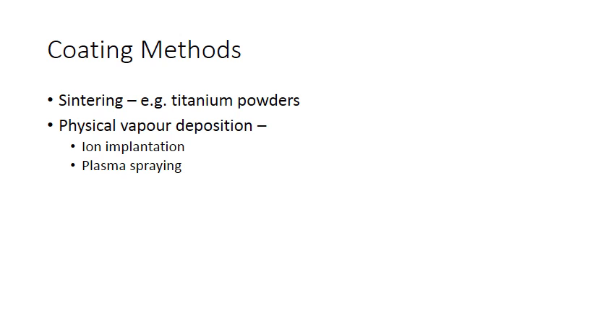Regarding how these coatings are applied: in the case of metal powders, sintering could be an option, as discussed in a previous video. The powder particles are heated to just below their melting temperature so they fuse together and fuse to the device, giving a rough surface finish. Cells prefer a rough surface finish and will integrate more readily to a rough surface than a smooth surface.